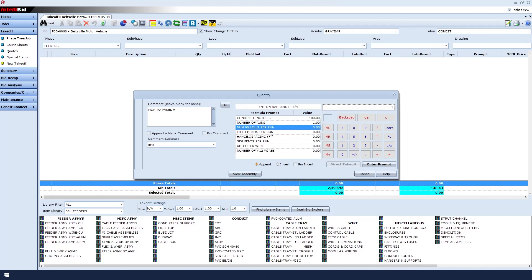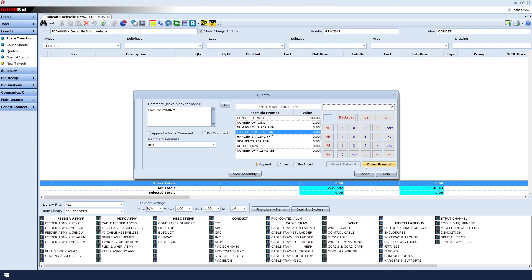Number of elbows. Number of field bends. If I select something for number of elbows, it's assumed I will be purchasing those elbows. But in this case, we're going to bend in the field. So the number of elbows will be zero. And then for field bends, we'll say it's going to be three. That will give me the labor to bend.